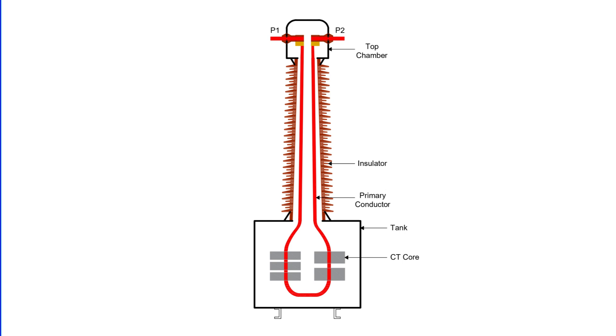Now here's the problem. Since the tank is grounded and the primary conductor is at high voltage, any failure in internal insulation can cause an arc to jump to the tank body. That's what leads to the violent explosions we often see when dead tank CTs fail.